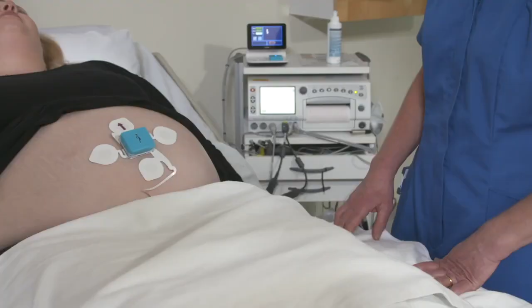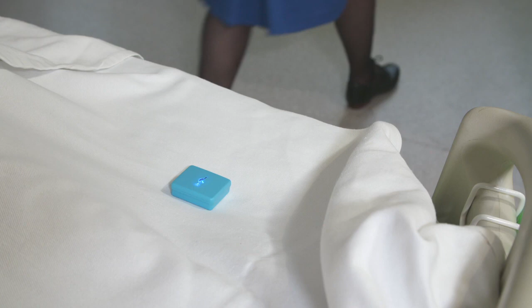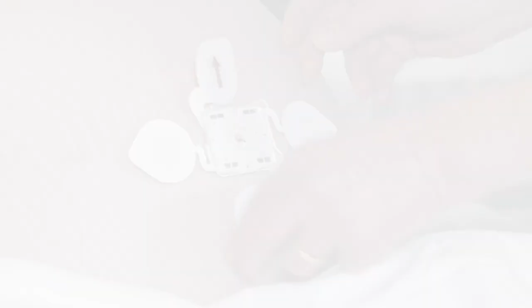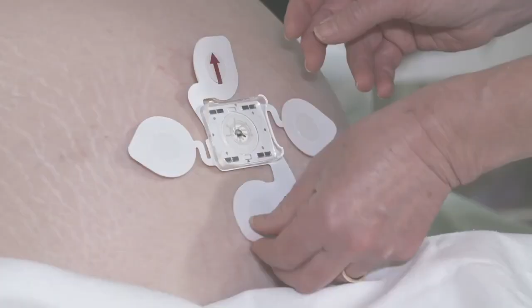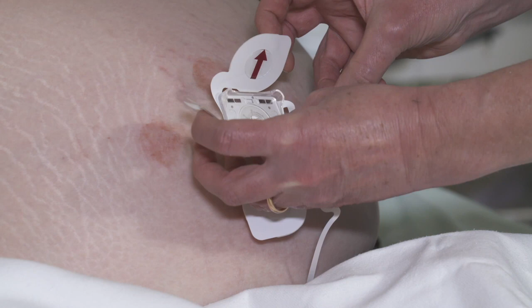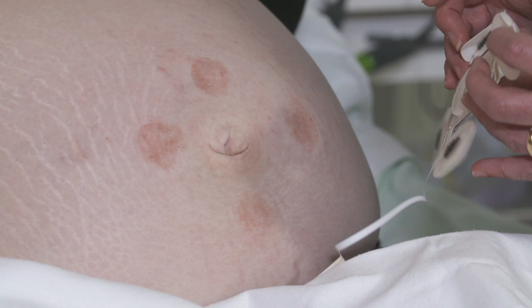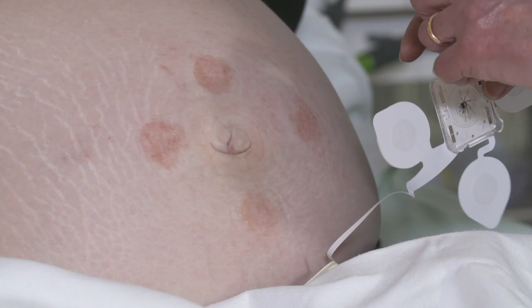It is very important that you always return the pod to the charging bay on the Novii interface, even if you have not had time to clean it. Leaving a pod on the bed or putting it to one side to deal with later may result in losing the pod. The patches are good for around 48 hours of monitoring, so you should tell the mom at the start that there may be some redness or itching under the electrodes so that she is not surprised. This will fade quickly. A severe allergic reaction is possible, although rare, and this is explained in Section 16 of the user manual.